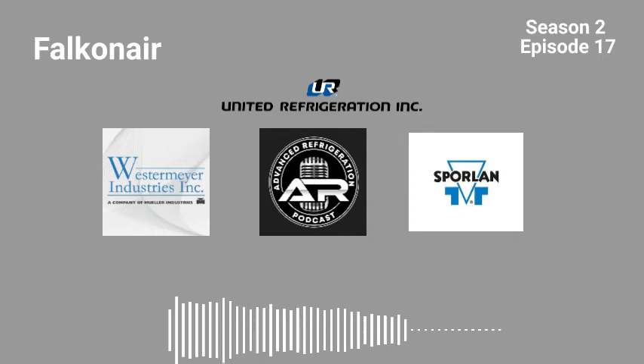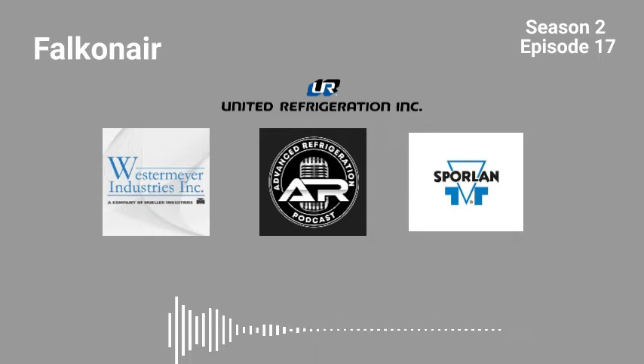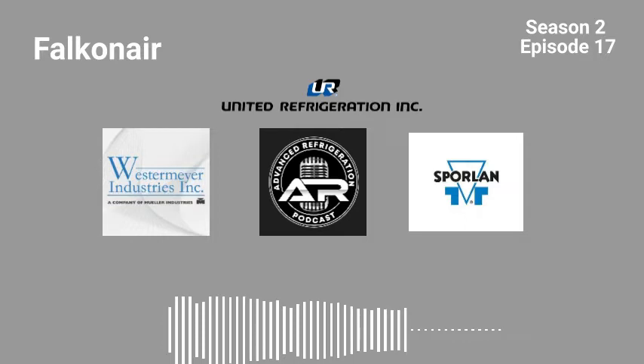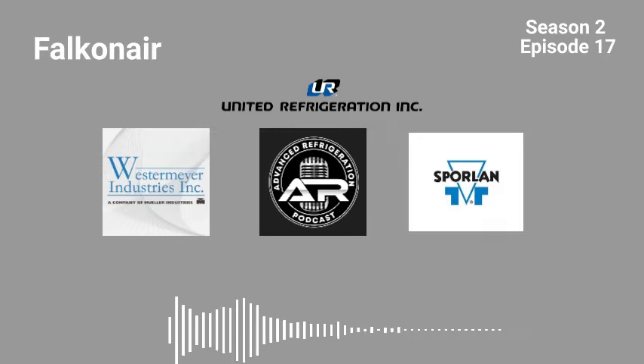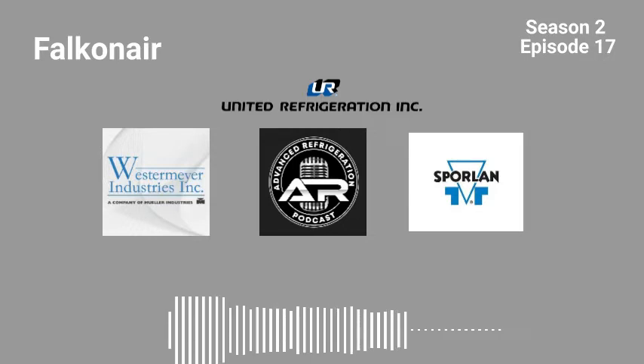Kevin, it took me a bit. Do you have it? I mean, it makes more sense that the original controller is still controlling it. I'm still trying to wrap my head around a single application, how it would actually know it's making box temperature besides the superheat being good. That's where I'm kind of wrapping my head around. You'd still need the conventional controls, say for a conventional unit. It's still going to have a pump down solenoid, is that correct? No, you still need everything the same. No, we don't. That's the beauty of our product, Kevin, and that's why everybody likes our product, because we're not messing with your existing controls.